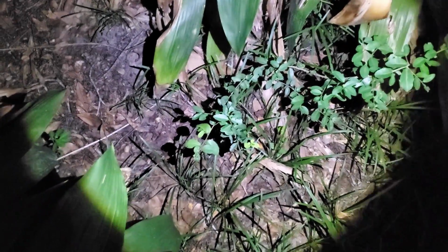You'd think that if there was a 3-gallon leak, because there was a 1-gallon leak out there, as I mentioned before, the leak that was obvious next to the meter, that was a 1 gallon per hour leak, and you could see the wetness. Like, you could see it getting all muddy. There's nothing here. I mean, you would see it soaking, you would see wetness. I just don't see it.